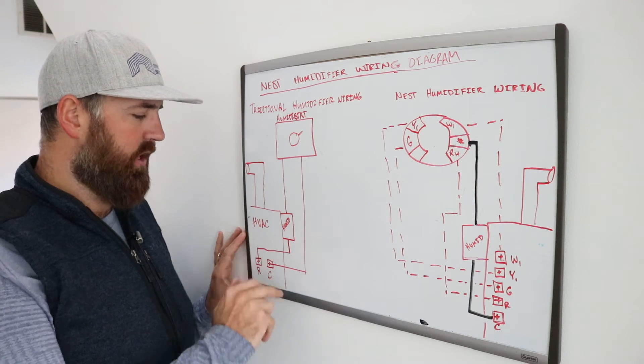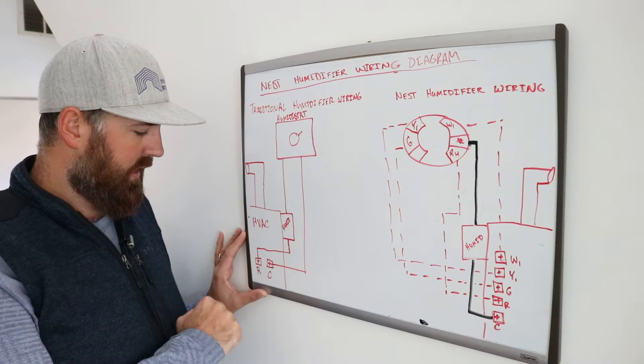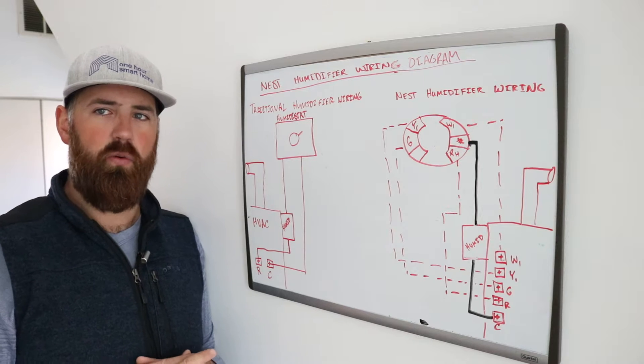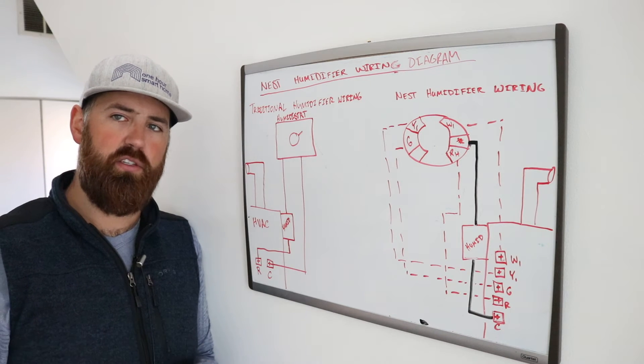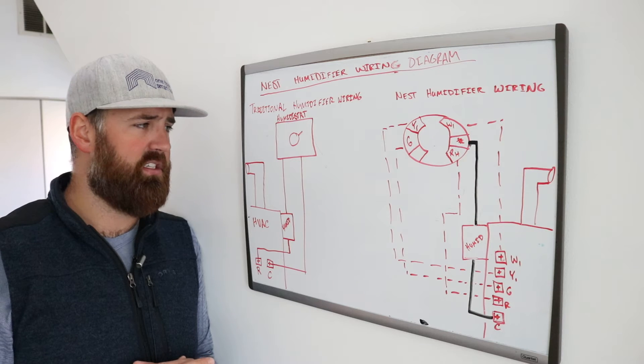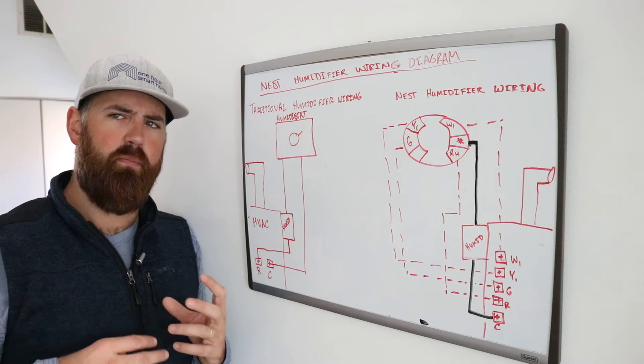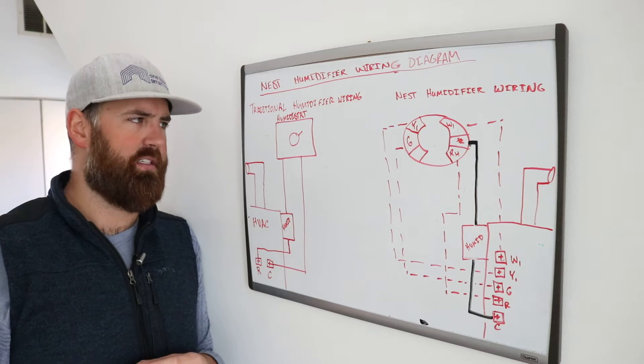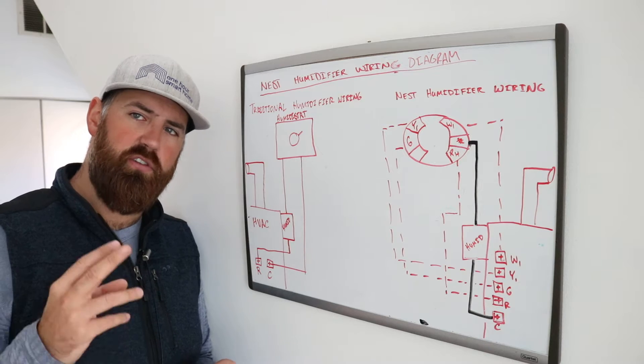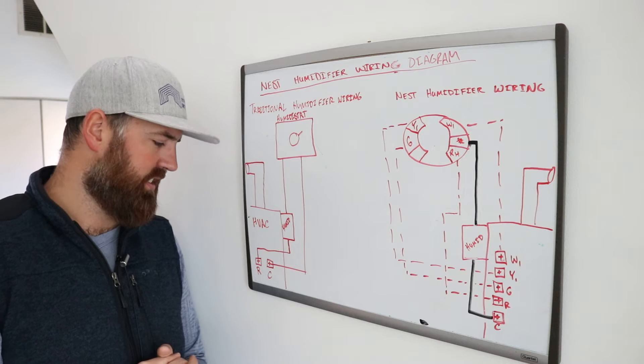So you've got your HVAC system here, I drew all this out, you've got your humidifier, that's this little block here. And how a humidifier works is that usually it's powered by 120 volts, it's got a little plug that plugs into an outlet near your HVAC system and that runs the fan on the humidifier if it's forced air or can power some of the other devices and things inside the humidifier. But it is activated by low voltage, 24 volts, typically from a humidistat or from your existing thermostat.